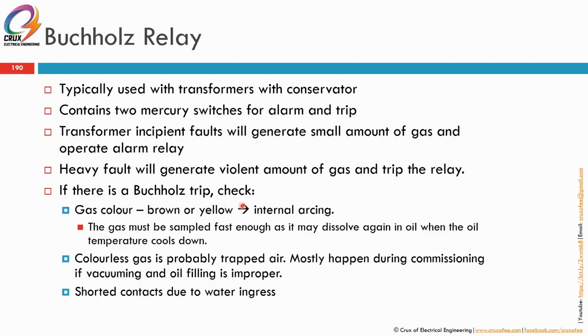If there is a Buchholz operation, these are the things that you should do. Please note the gas color, whether it's brown or yellow, as it could be due to internal arcing. Once you see this gas, you must sample the gas as fast as possible. If not, the gas may dissolve again in the oil when the oil temperature cools down. Normally, after tripping due to Buchholz, even if you see gas inside the Buchholz compartment, after 2 to 3 hours the gas would have dissolved and the oil would have filled up that area again. So the gas must be sampled fast enough.